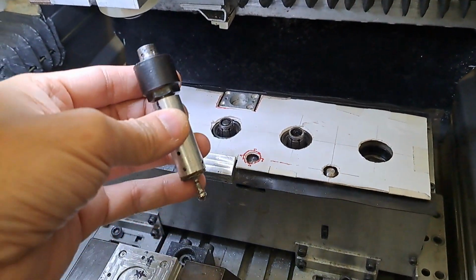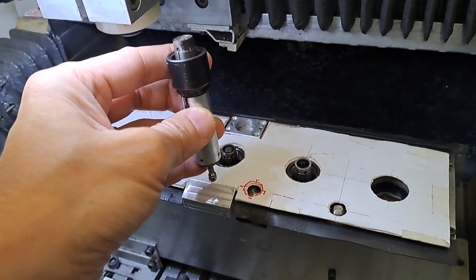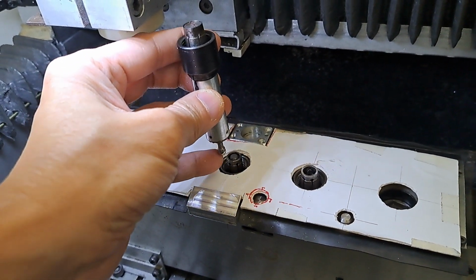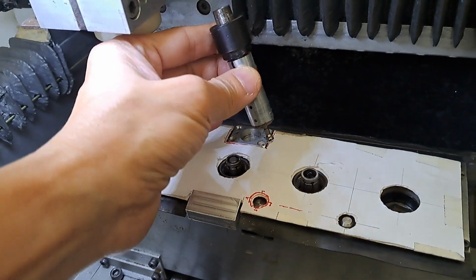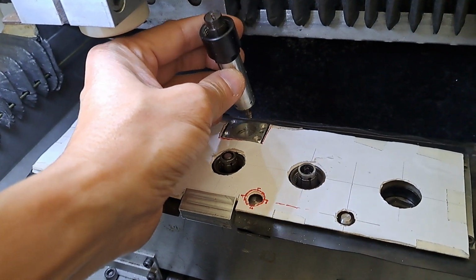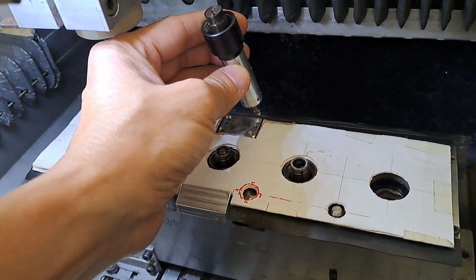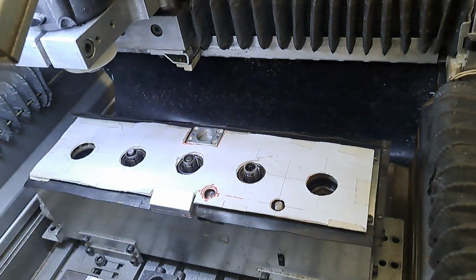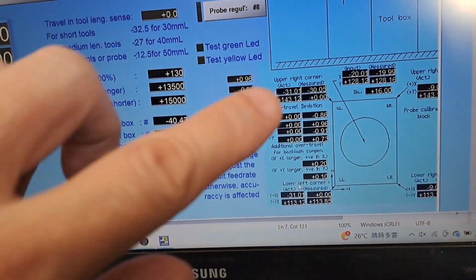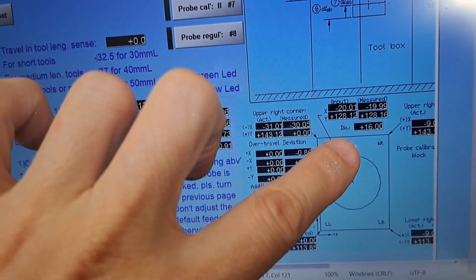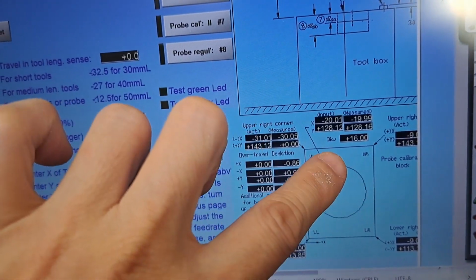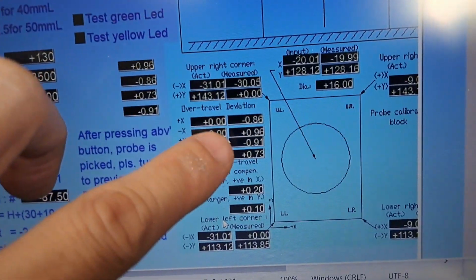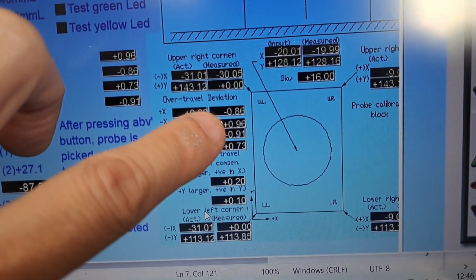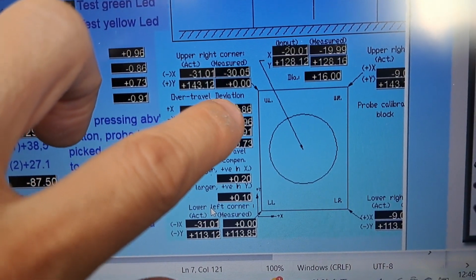In the one operation in calibrations, this touch probe will touch 4 sides of this reference box and get its xy value, and it will compare internally with the true values, then have the differences to put here.